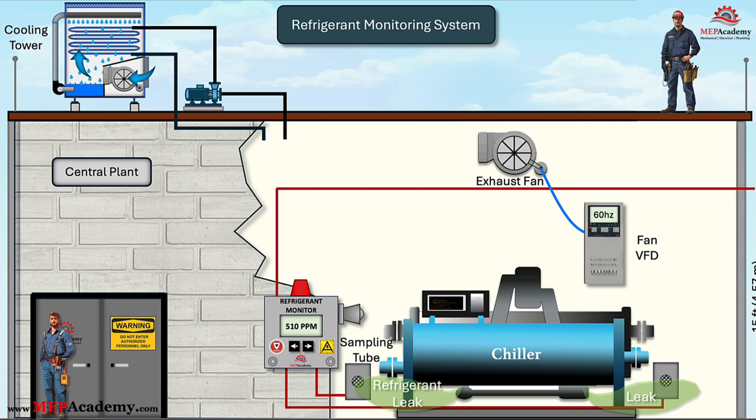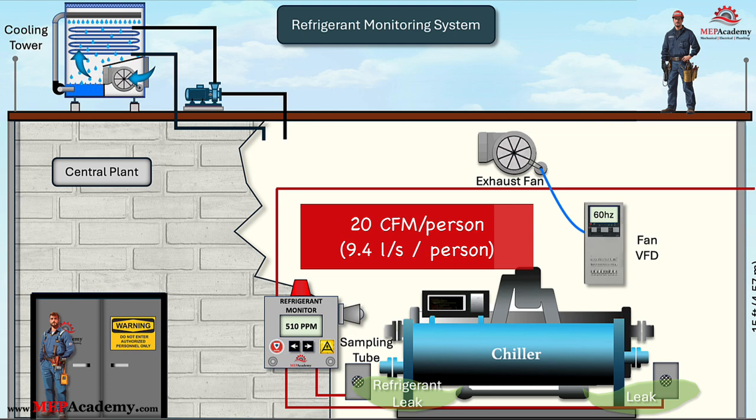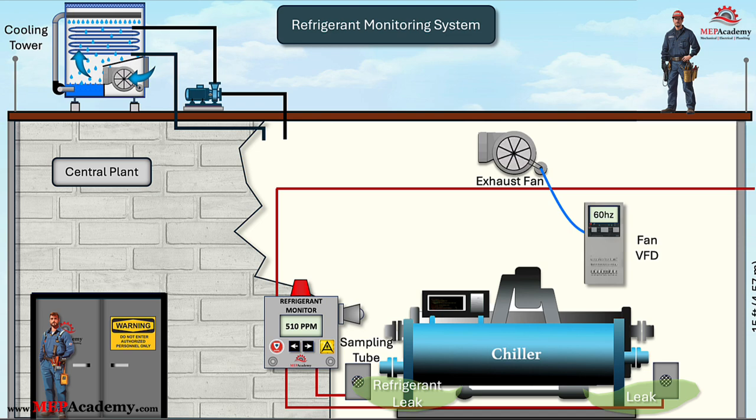Minimum ventilation requirements: when the machinery room is occupied, the ventilation system should operate at minimum speed or at a rate of at least 0.5 cubic feet per minute per square foot of room area (2.54 liters per second per square meter), or 20 CFM (9.4 liters per second) per person present, whichever is greater. This ensures that fresh air circulates adequately, preventing the accumulation of refrigerants or other harmful gases.